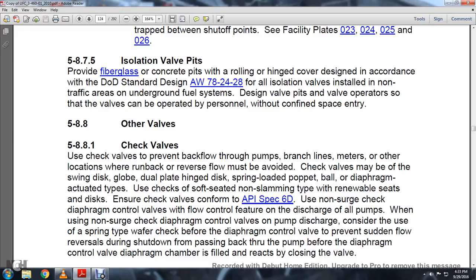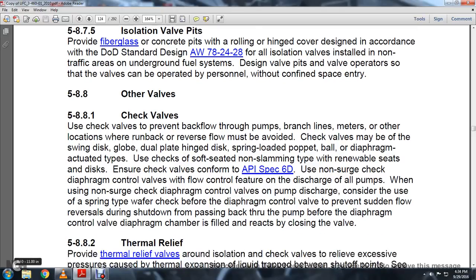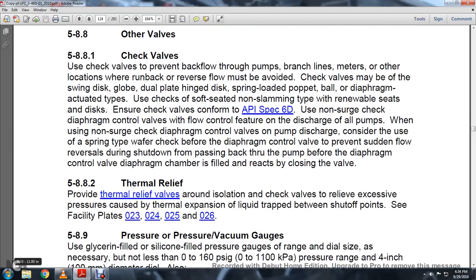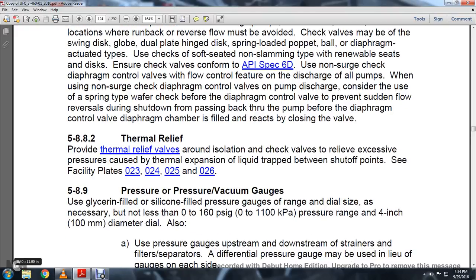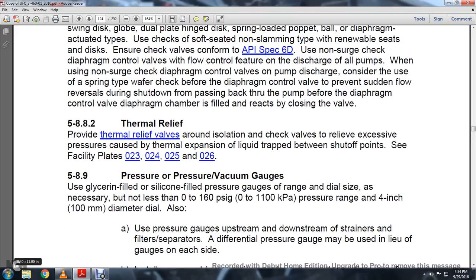Use non-surge check diaphragm control valves for the flow control feature at the discharge of all pumps. When the non-surge check diaphragm control valve is at the discharge, consider a spring-type check valve before the diaphragm control valve to prevent sudden flow reversal during shutdown, passing back through the pump and the diaphragm control valve. The diaphragm chamber is filled, which reacts with the closing of the valve.